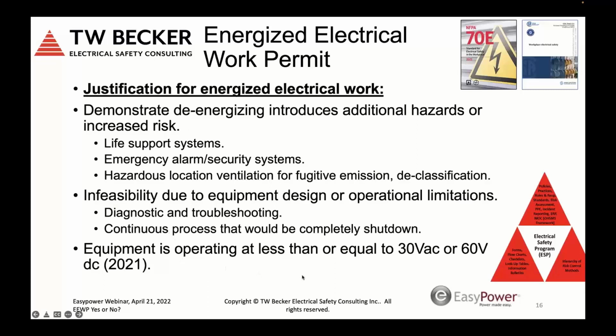Now, as far as equipment voltage, what I've listed, and I forgot to update this, is equipment operating at less than or equal to 50 volts AC or DC in 70E. But in Canada, we changed those low voltage thresholds to 30 volts AC or 60 volts DC in the 2021 edition. This has been moving around in 70E, but ultimately OSHA has a 50 volt threshold AC and DC, so until we can get OSHA updated, the actual voltages won't change in 70E. We're not subject to that level of oversight in Canada, so we put in voltages determined based on electrical hazard classification. There's a whole other webinar on electrical hazard classification and these voltages of concern for a shock occurring or sustaining an abnormal arcing fault. But if your voltages are less than 50 volts AC or DC in the US, or 30 volts AC or 60 volts DC in Canada, we don't need justification.